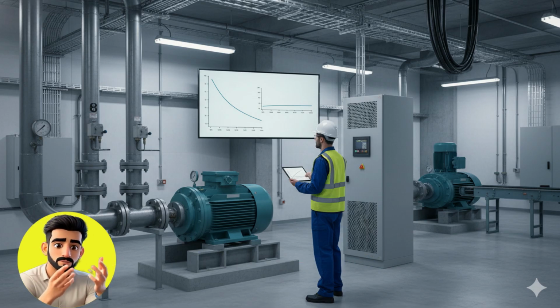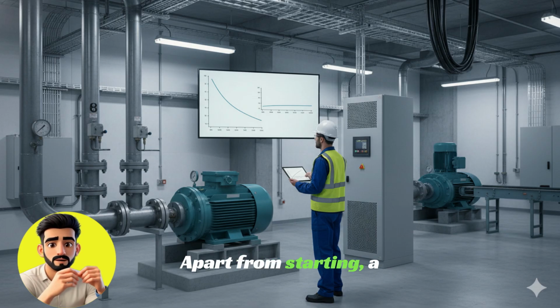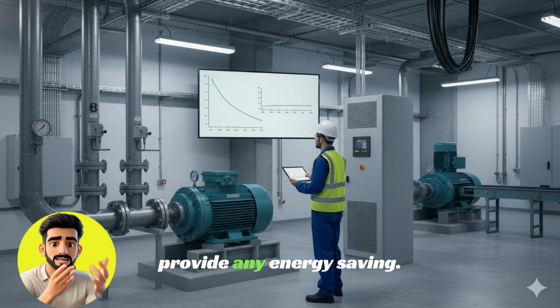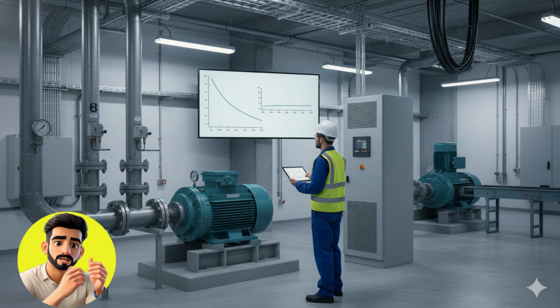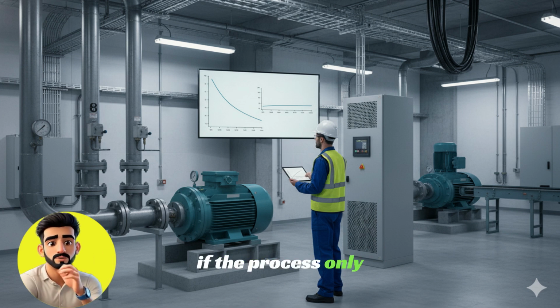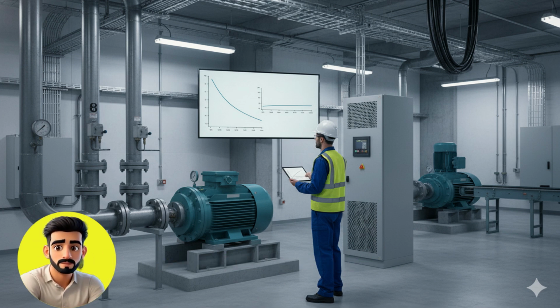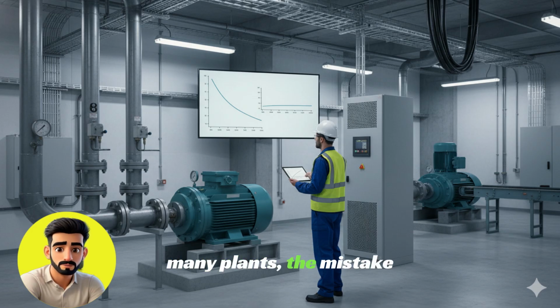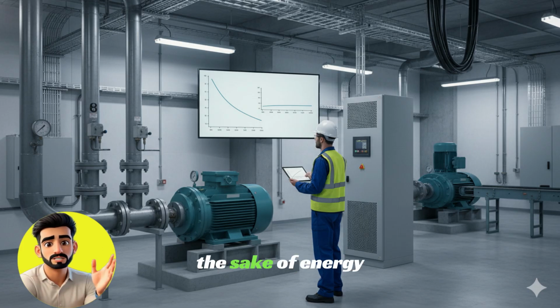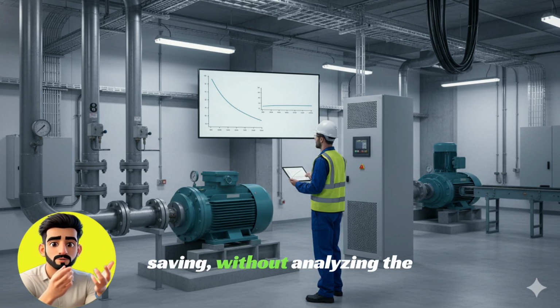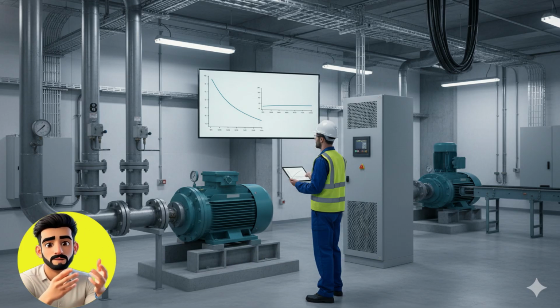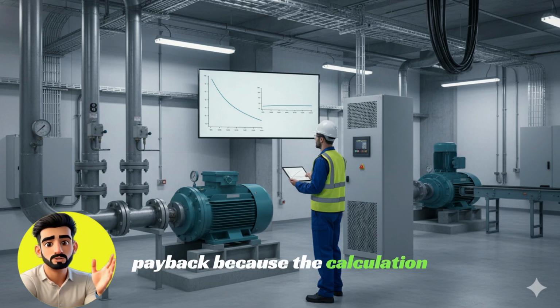And the soft starter? Apart from starting, a soft starter does not provide any energy saving. The motor will run at full speed even if the process only requires 50% flow. That is why in many plants, the mistake is that they first install VSD just for the sake of energy saving without analyzing the load type. And later they say they did not get payback. They did not get payback because the calculation was wrong.